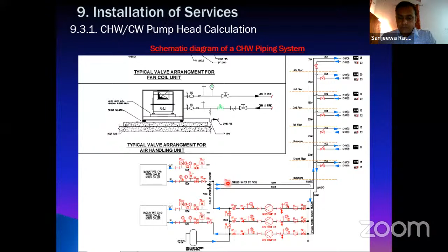Then again, when you install the pumps, you also need to identify the NPSH. NPSH means net positive suction head. There are two terms: one is NPSHA and the other is NPSHR. NPSHR means net positive suction head required. That's a property defined by the pump manufacturer. It's a requirement for the pump to operate smoothly.